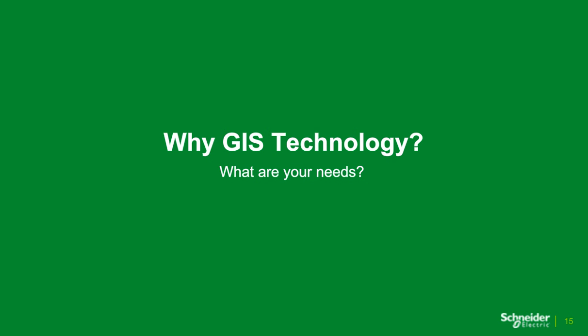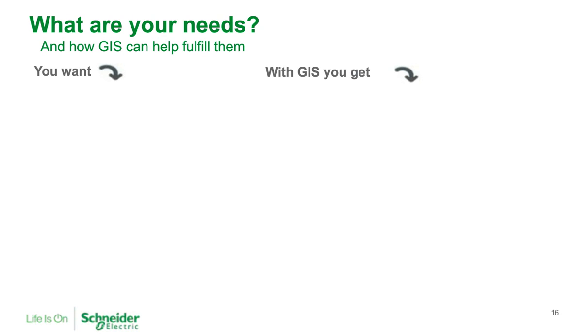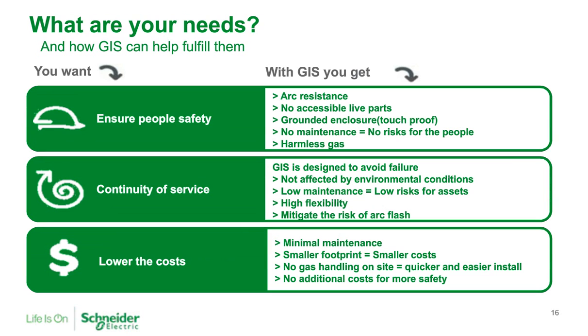So moving forward, I have some general slides just to talk about why we use GIS. We've already talked about one of them. Looks like I've got to work on some of these animations here. So there are three main things that I want to focus on for GIS. One is we want to ensure people's safety. With GIS, you get arc resistance. Most products on the market are arc resistant, either to the IEEE standard or to the IEC standard for arc resistance. And because it's a sealed pressure system, there's no maintenance inside the medium voltage compartment. And because there's no maintenance there, workers are no longer exposed to the risks of working on medium and high voltage components.